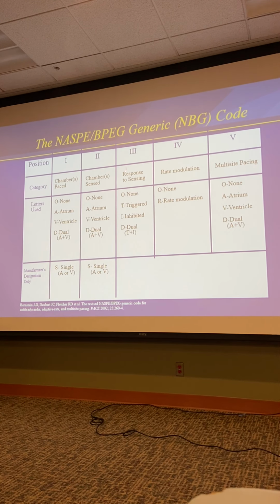If someone's old and frail, we may go lower than that, and if someone's young and athletic, we may go higher. Rate adaptive pacing we talked about a moment ago. We can program the AV delay. Every time it sees a P wave, there's a fixed amount of time before it expects to see a QRS, or else it will provide one. The AV delay is how long it waits after providing an atrial event before it paces the ventricle. That can be fixed. Typically, we might say it's like a normal PR interval, 120 milliseconds, something like that.